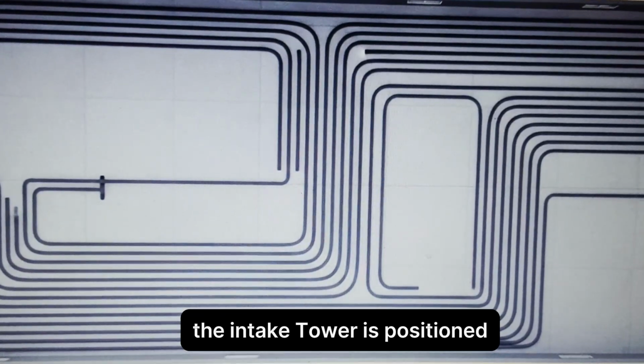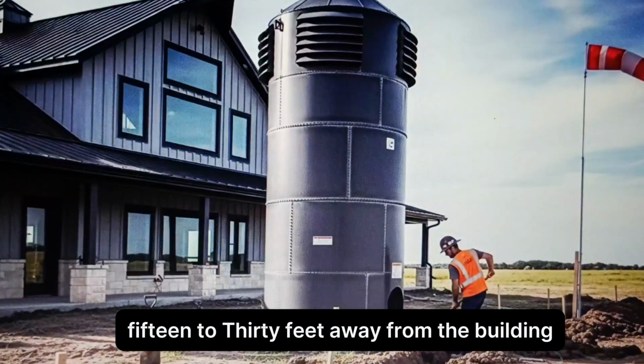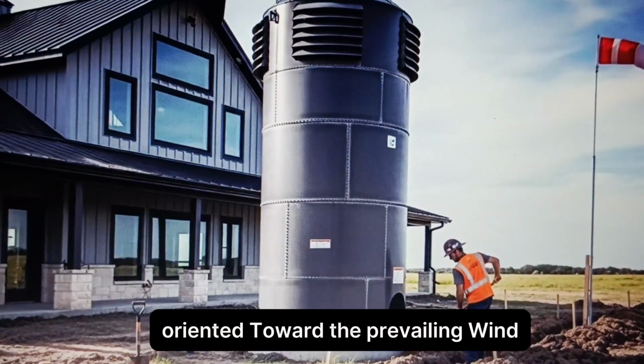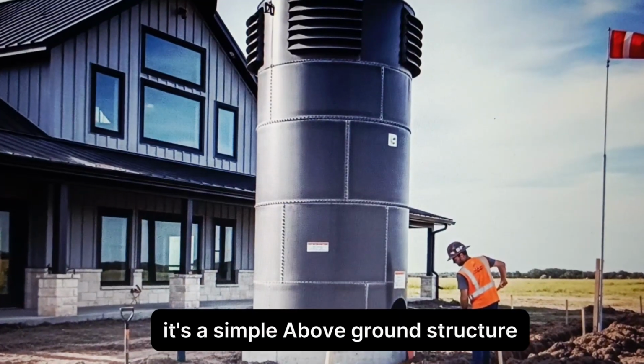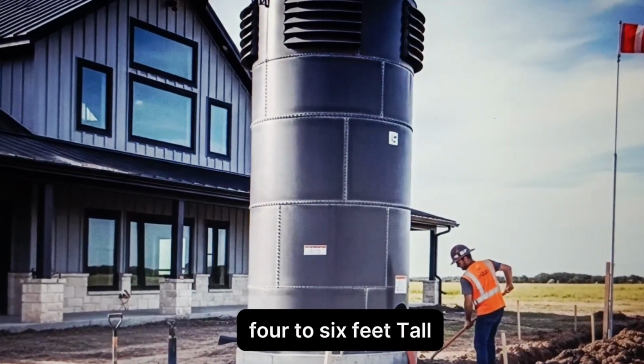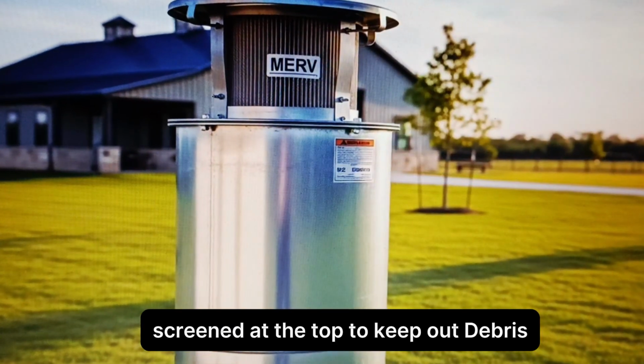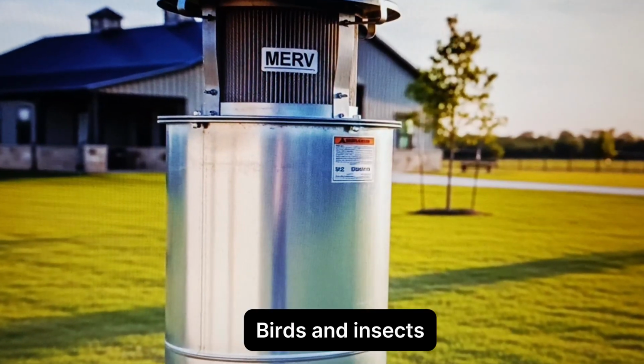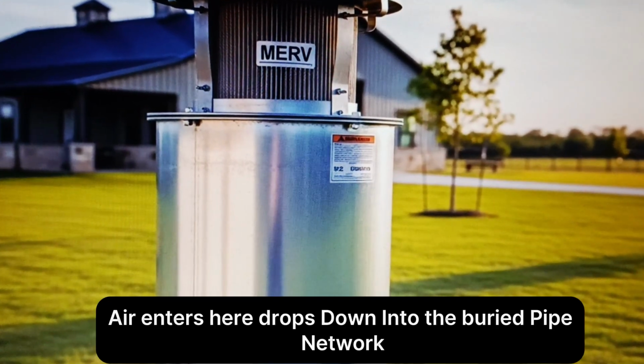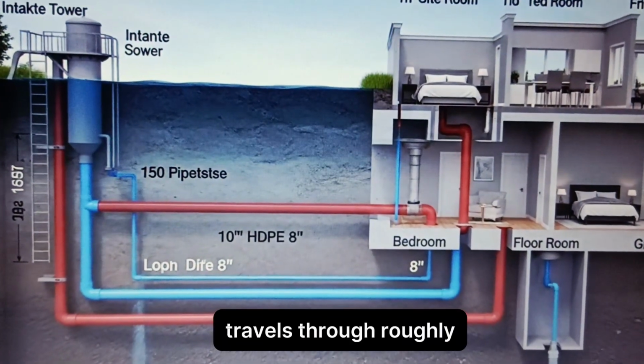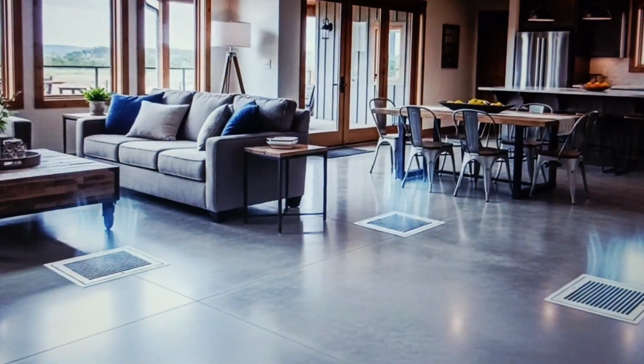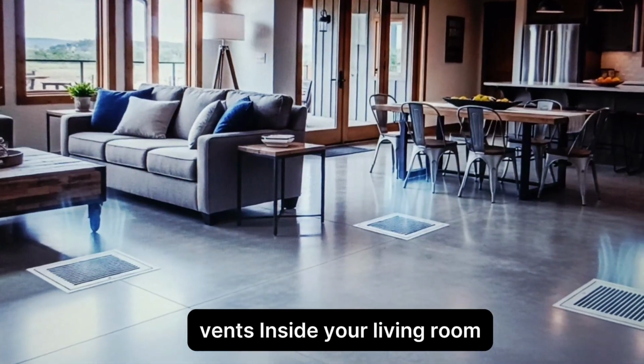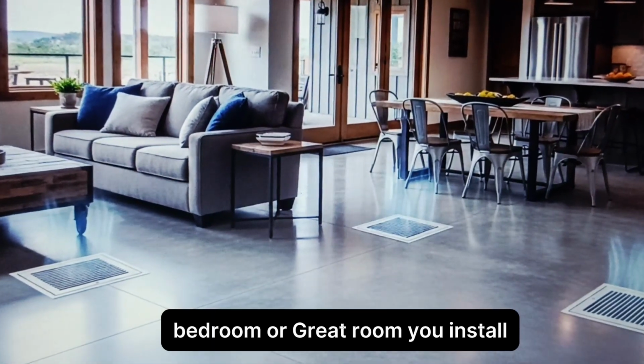The intake tower is positioned 15 to 30 feet away from the building, oriented toward the prevailing wind. It's a simple above-ground structure, 4 to 6 feet tall, screened at the top to keep out debris, birds, and insects. Air enters here, drops down into the buried pipe network, travels through roughly 150 feet of earth-coupled pipe at 8 feet deep, and emerges through floor vents inside your living room, bedroom, or great room.